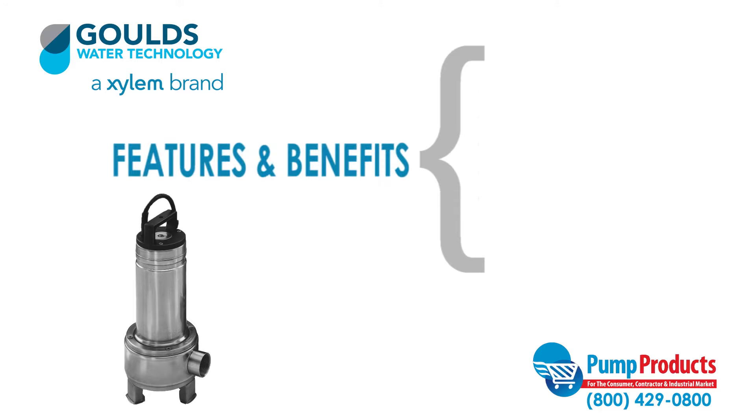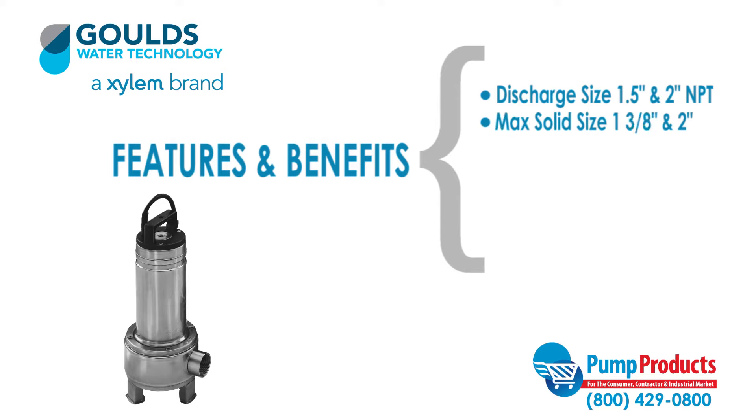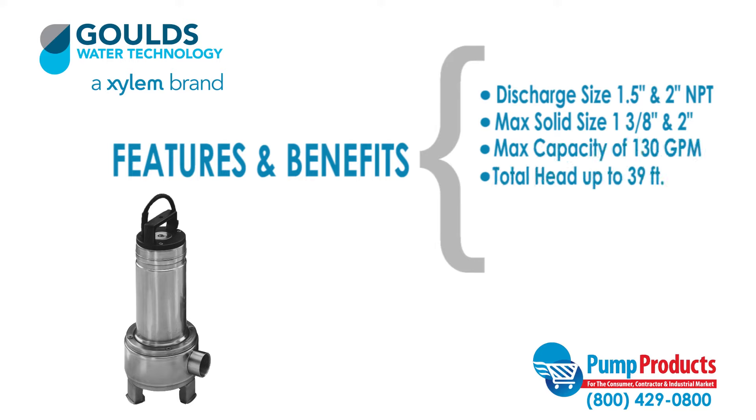Some features and benefits of this series include a discharge size of one and a half inches or two inches NPT. Maximum solid size of one and three eighths inches for one half horsepower models and two inch solids for three quarter horsepower models and larger. A maximum capacity of 130 GPM. Total head up to 39 feet.